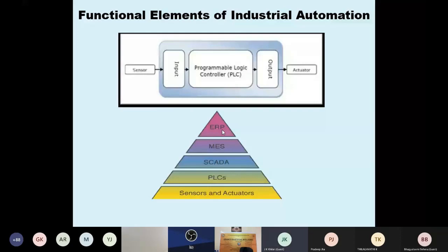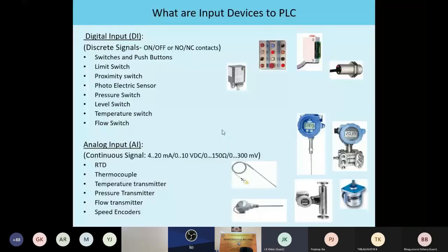Then these are the inputs of the PLCs. One is limit switch, proximity switch, photoelectric sensor, pressure switch, level switch, temperature switch, flow switch. Switch means the input is digital. Digital will give either a low voltage level or a high voltage level. And the analog inputs are thermocouple input, RTD input, temperature transmitter, pressure transmitter, flow transmitter, speed encoder, like this. These are known as analog inputs.